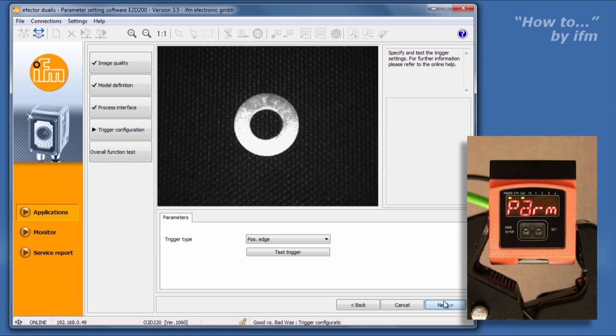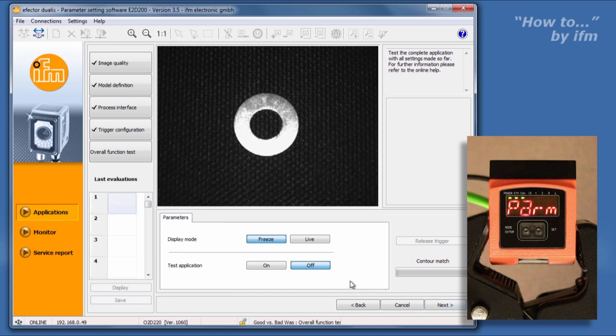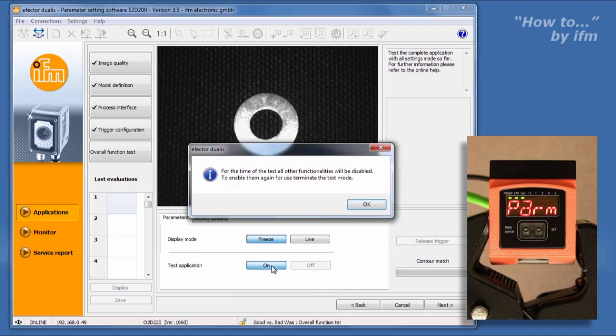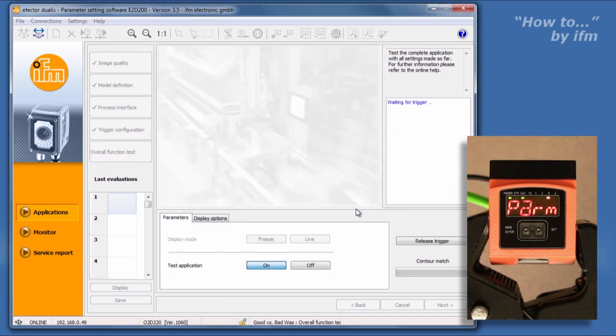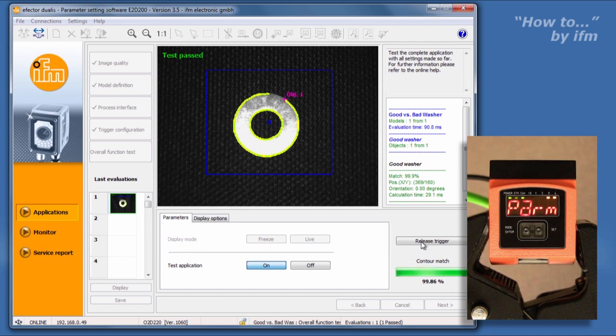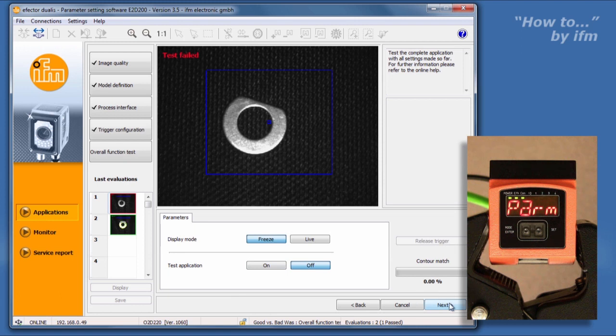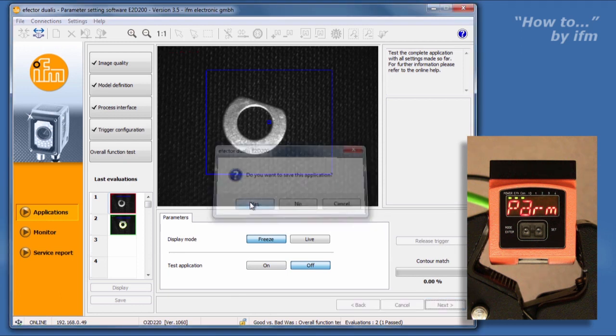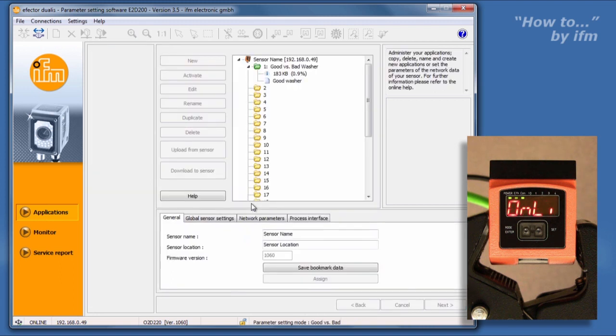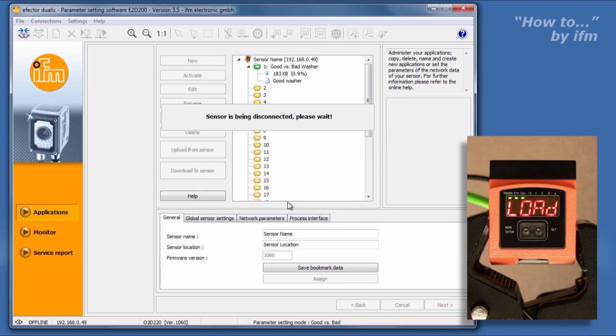The final step is to perform an overall function test, which must be completed before the application can be saved. With our good part in place, click the Test Application On button. A message will be displayed to inform you that other functionality of the software will be disabled during the test. Click Release Trigger, and the O2D will take an exposure. Replace the good part with a failed part, and click Release Trigger a second time. With both a positive and negative test verified, deactivate the test with the Off button. Click Next and save your application. You will see that your folder in the list is now green, meaning it contains the currently running application. When disconnecting the O2D from the software, be sure to select Disconnect from the Connections menu. That completes the basic setting of the O2D.